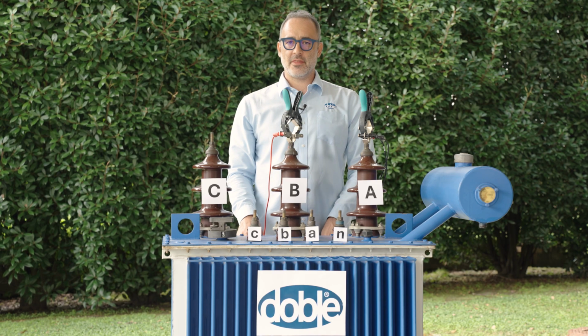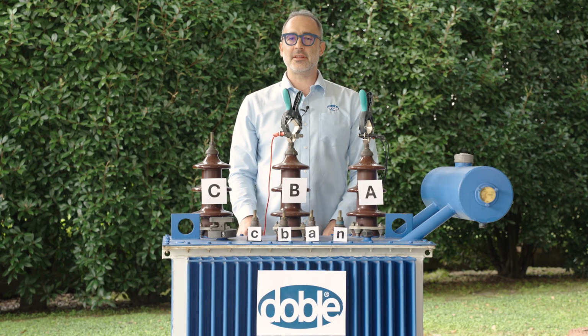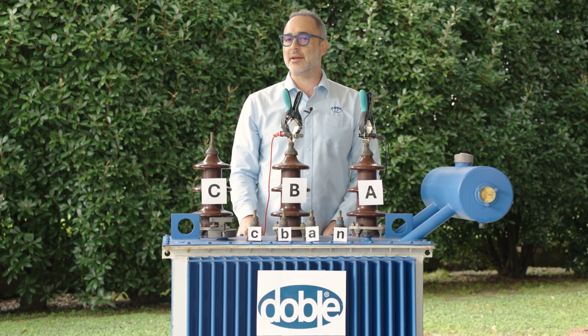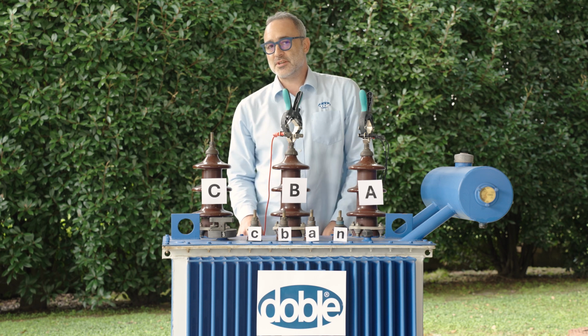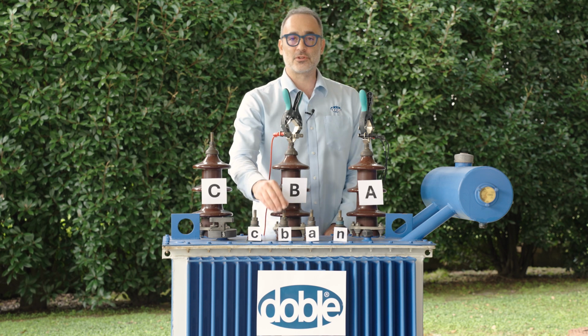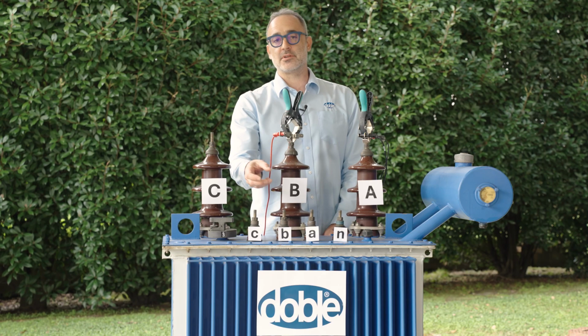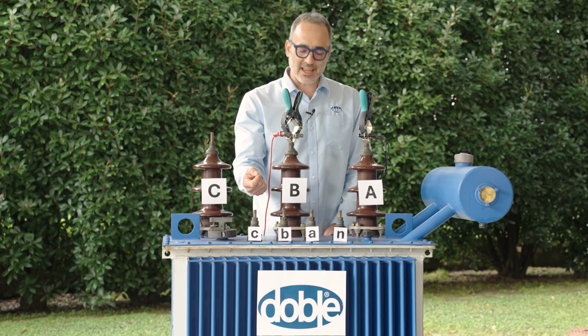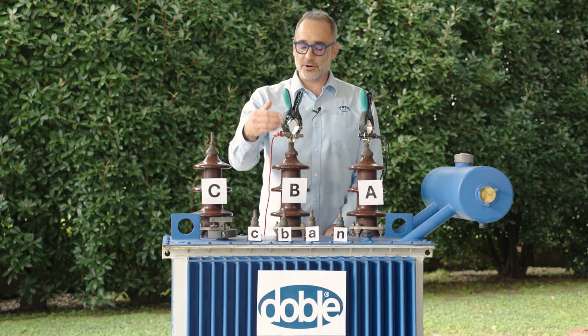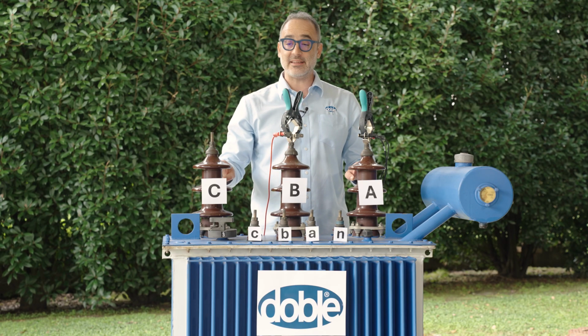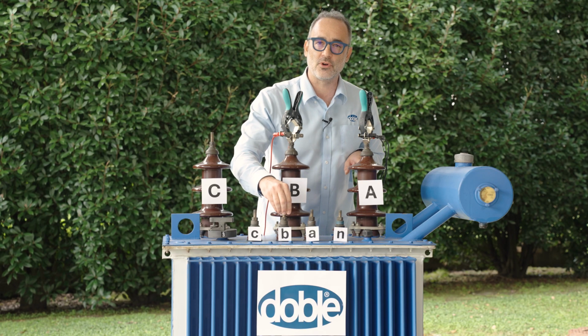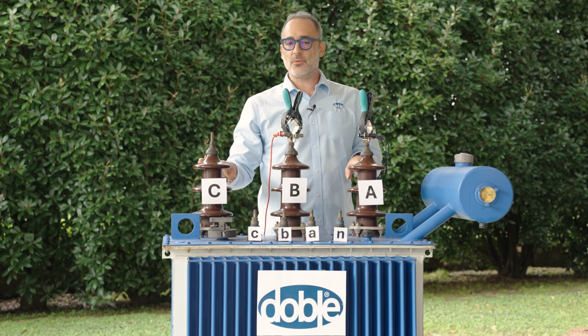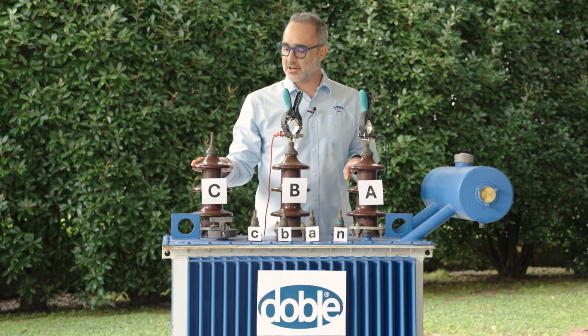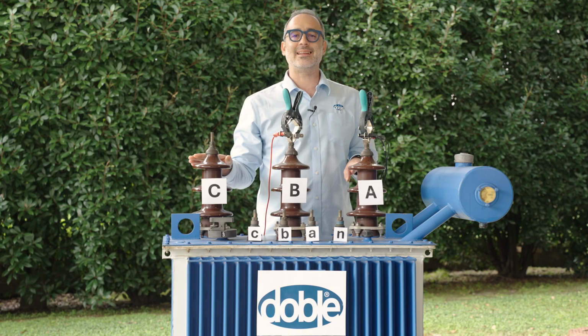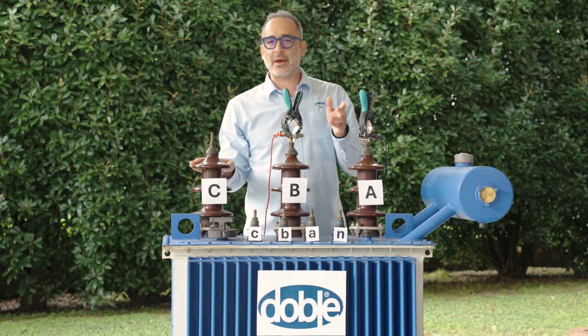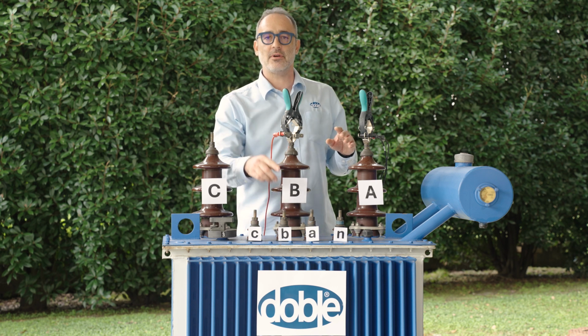So we measured now the secondary side, and we've seen that the resistance of the secondary side is very small, 10 milliohms. Why is it small? As mentioned before, because on the secondary side the voltage is lower, but the current is higher, because the power needs to be the same or very close to the power on the primary side. But on the primary side we have 18.5 kilovolts. Here we have 400 volts. So, not necessarily proportionally, but generally the resistance of the primary side is higher. In this case, I'm expecting about 40 ohm, versus 10 milliohm.